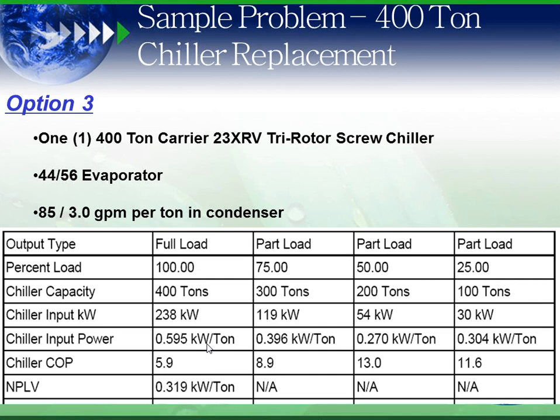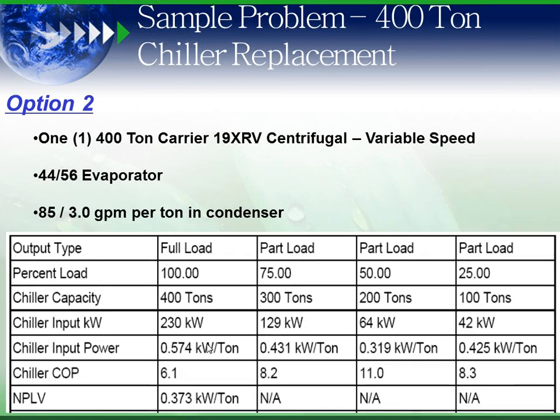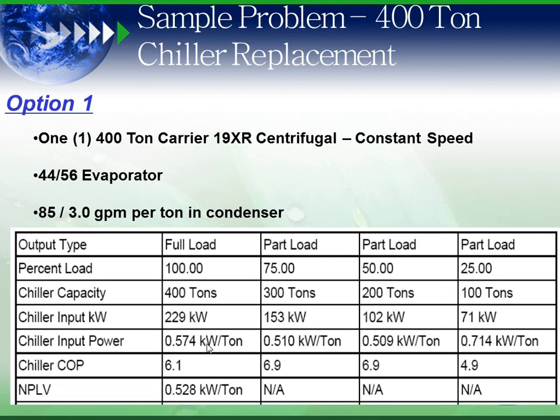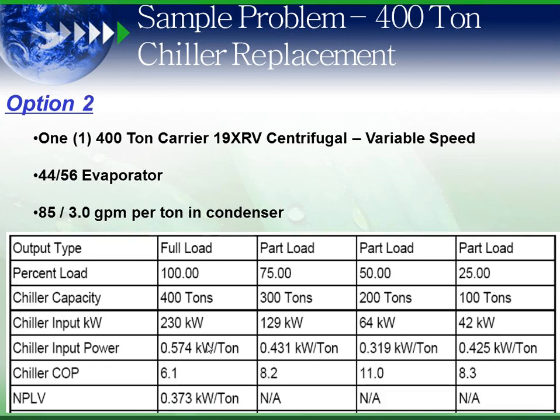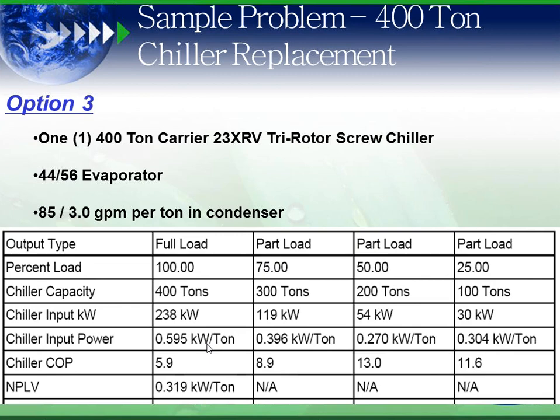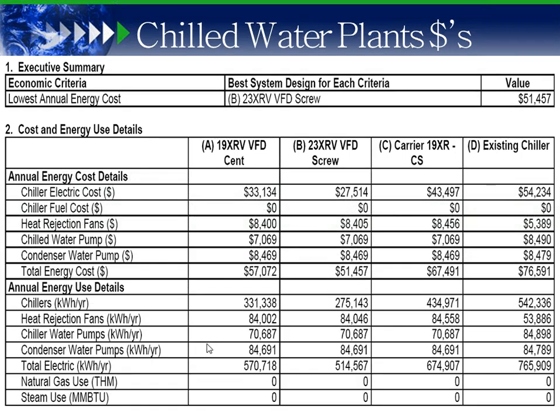Again, here's option 3, 400-ton 23XRV tri-rotor screw, 0.595 full load, 0.319 part load. Again, look at the part load data: 0.528 on constant speed, 0.373 centrifugal variable speed, 0.319 23XRV tri-rotor in parallel with the existing system. Let's do a little analysis and look at what happens to the system itself.